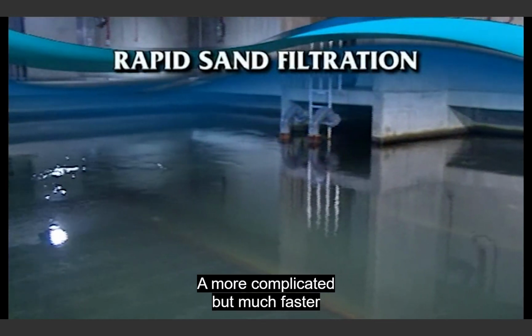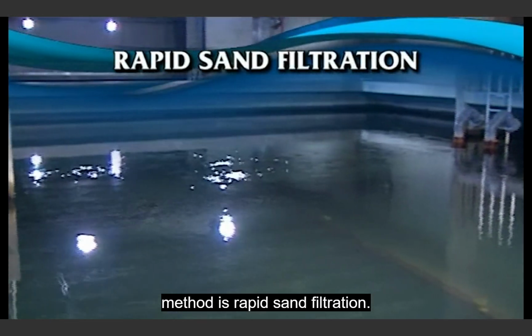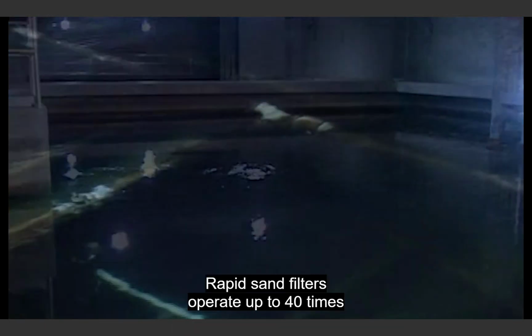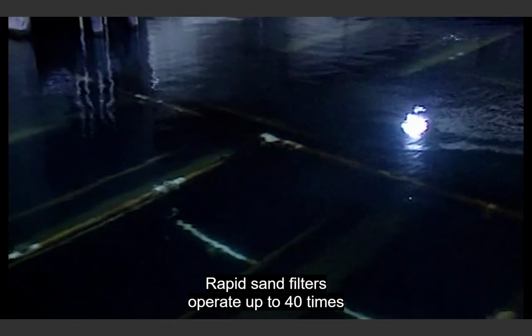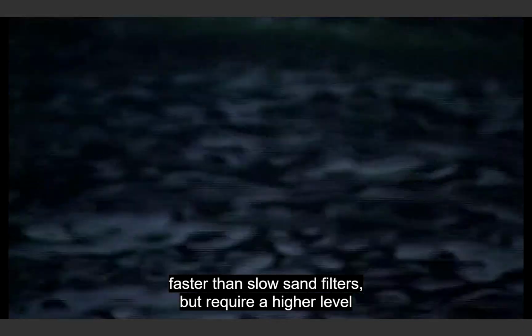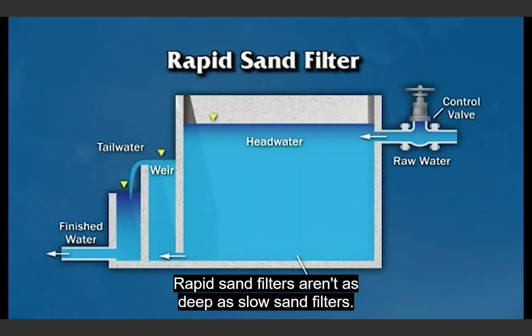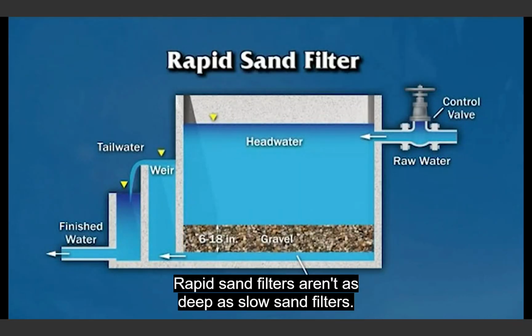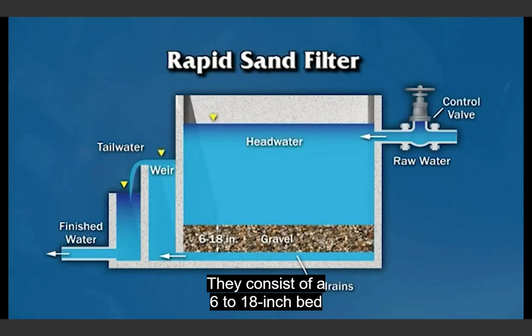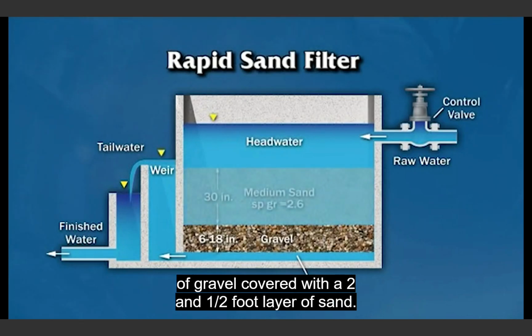A more complicated but much faster method is rapid sand filtration. Rapid sand filters operate up to 40 times faster than slow sand filters, but require a higher level of monitoring and control. Rapid sand filters aren't as deep as slow sand filters. They consist of a 6 to 18-inch bed of gravel covered with a 2.5-foot layer of sand.